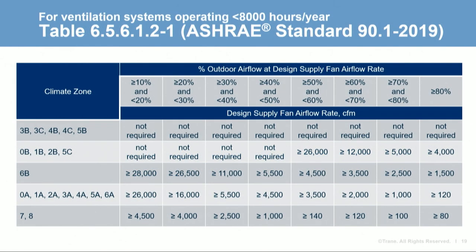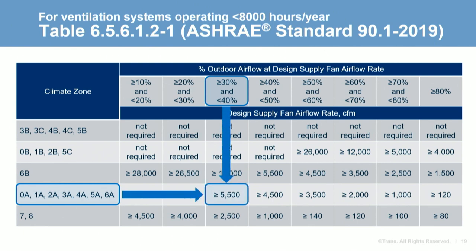To demonstrate, here's a table that applies to a system operating less than 8,000 hours per year. Consider a building in climate zone 3A: if the system is designed for 35% outdoor air, exhaust air energy recovery will be required if the design supply airflow is 5,500 CFM or larger. In general, for higher percentages of outdoor air, exhaust air energy recovery is required on smaller and smaller systems. But in mild climate zones, it may not be required at all.